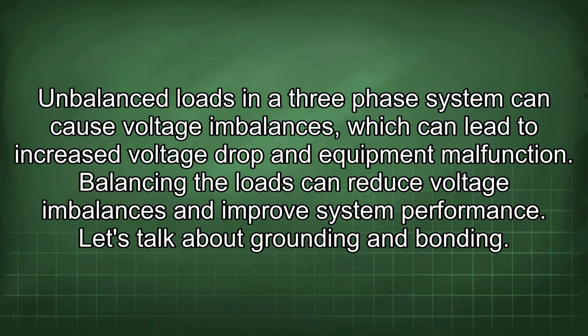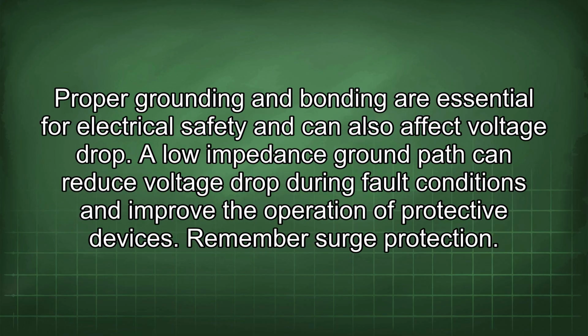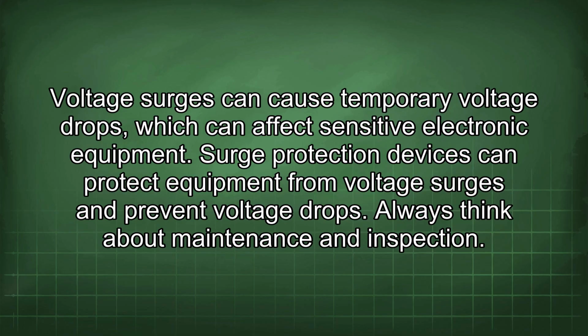Let's talk about grounding and bonding. Proper grounding and bonding are essential for electrical safety and can also affect voltage drop. A low impedance ground path can reduce voltage drop during fault conditions and improve the operation of protective devices. Remember surge protection. Voltage surges can cause temporary voltage drops, which can affect sensitive electronic equipment. Surge protection devices can protect equipment from voltage surges and prevent voltage drops.